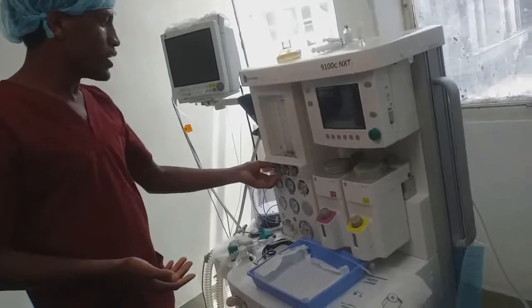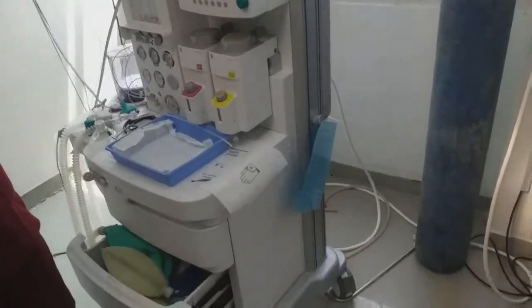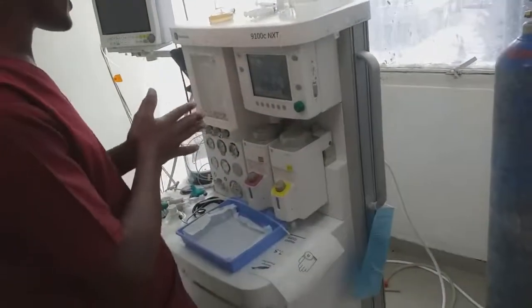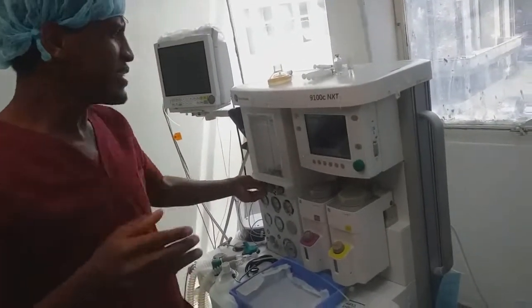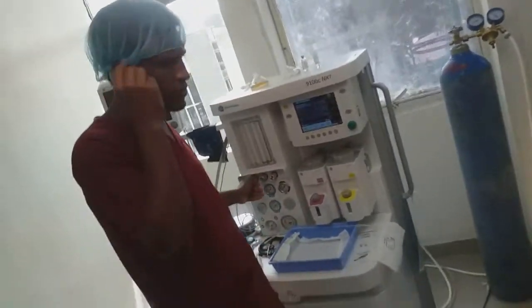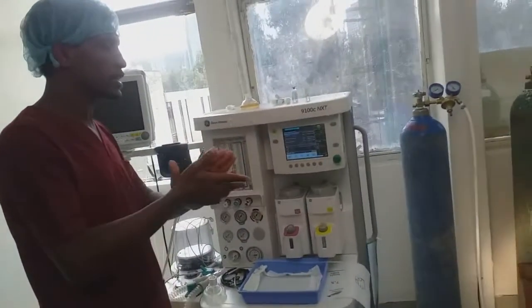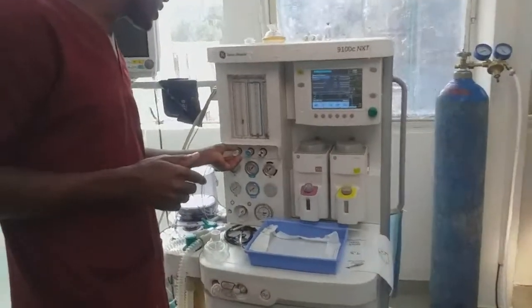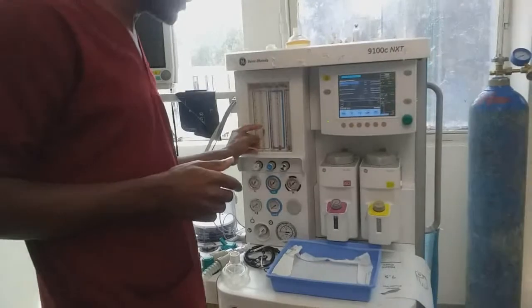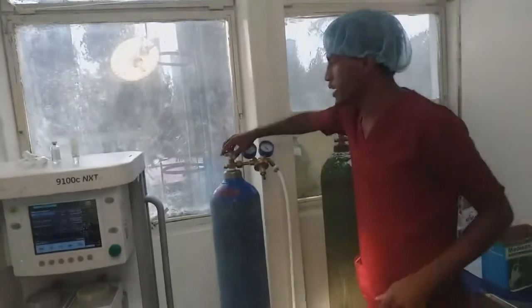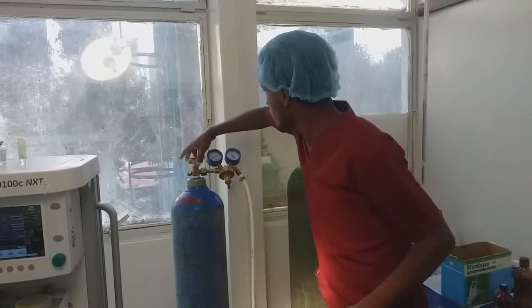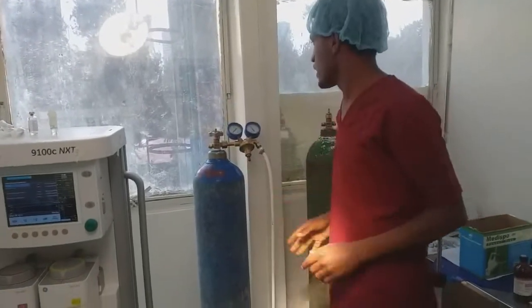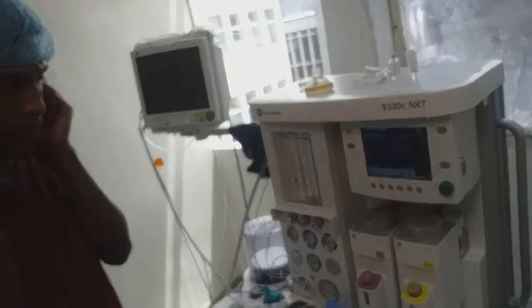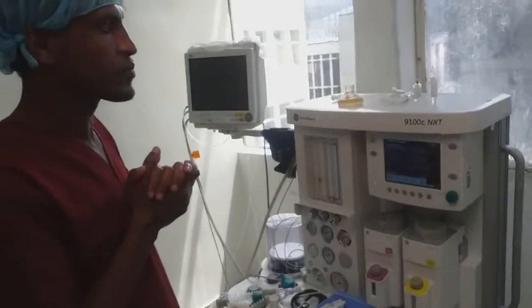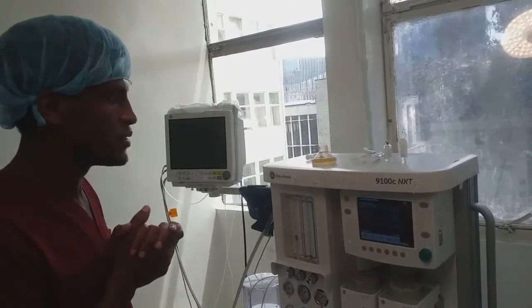Now I'm going to check the oxygen pressure failure alarm. This pressure-driven alarm is recommended for all machines. It alerts us to do something. Now to check the oxygen alarm, I have opened oxygen, flow meter at 4. Now I am going to close the cylinder. I am going to close the oxygen cylinder. I already closed the oxygen cylinder. I have to hear some alarm now. Just wait for a moment.